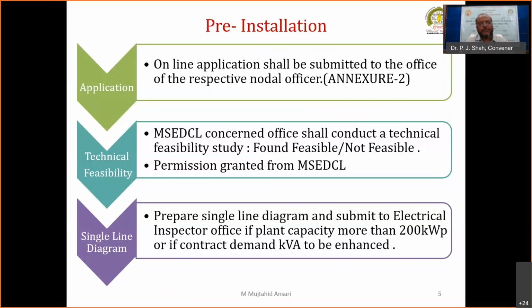Now, the single line diagram shows where you are going to connect the solar power, where you are going to inject the power. So it is necessary to draw the single line diagram. If the capacity is more than 200 kilowatt, then we have to take the permission from the chief electrical engineer, electrical inspector wings from the region or from the district. Otherwise, if the plant capacity is less than 200 kilowatt, then your concerned circle office, called the superintending office in Maharashtra, in every district, grants the permission. So this is related to the pre-installation activity involved in the installation of a solar power plant.